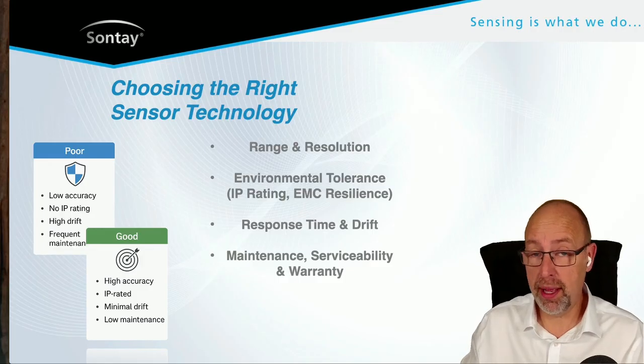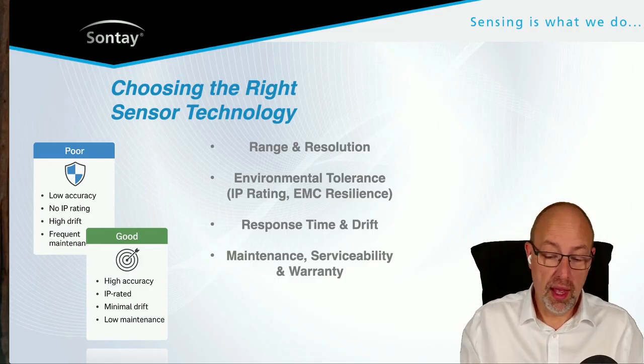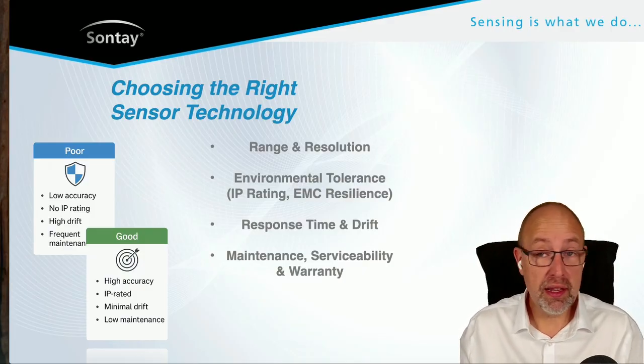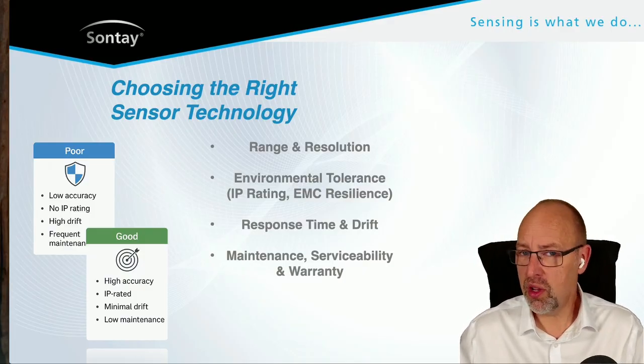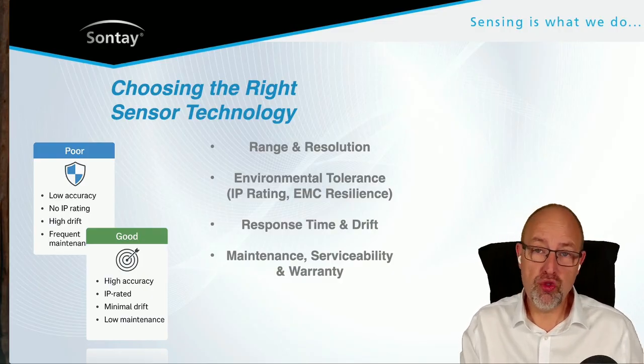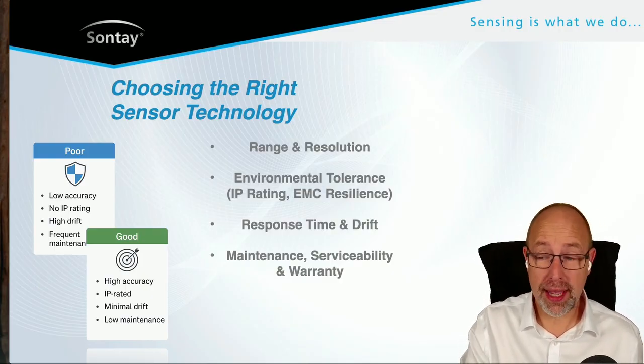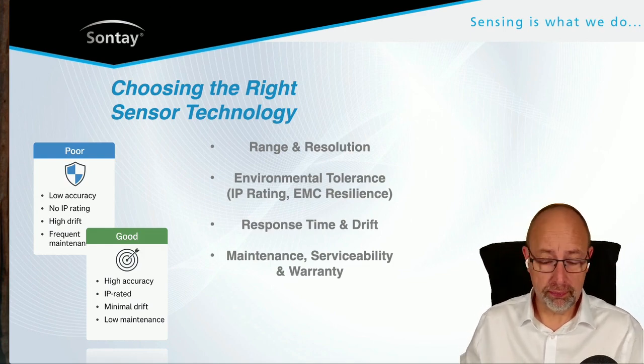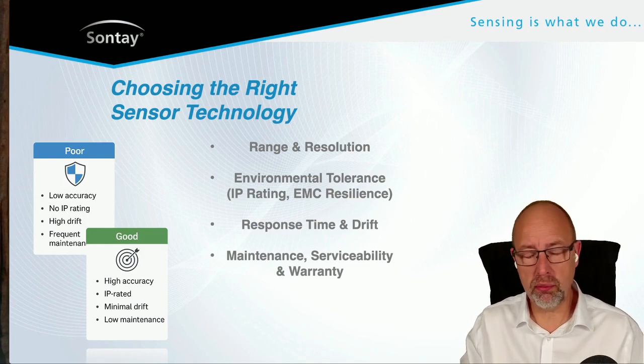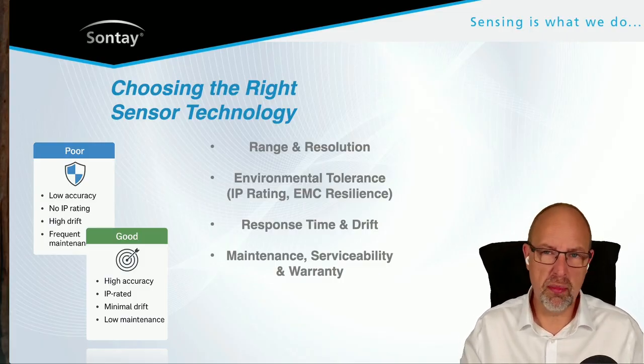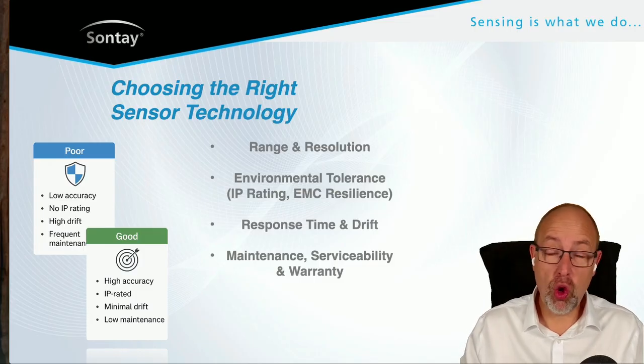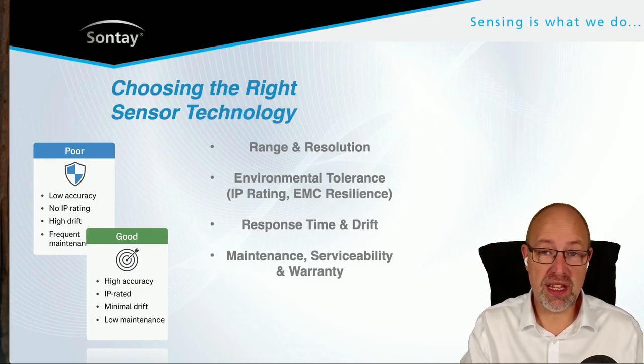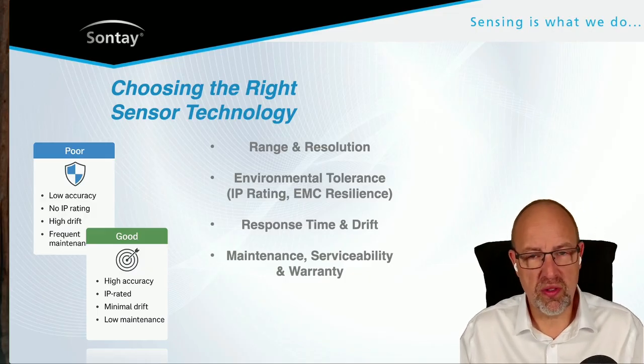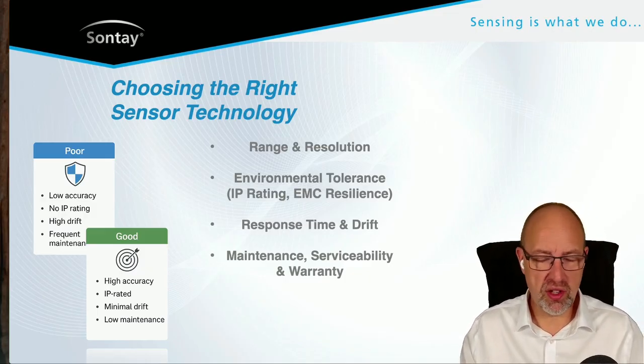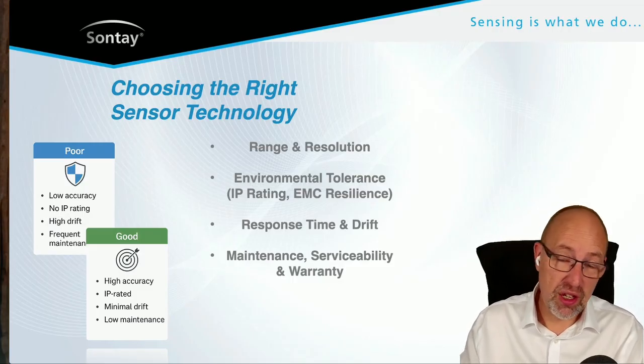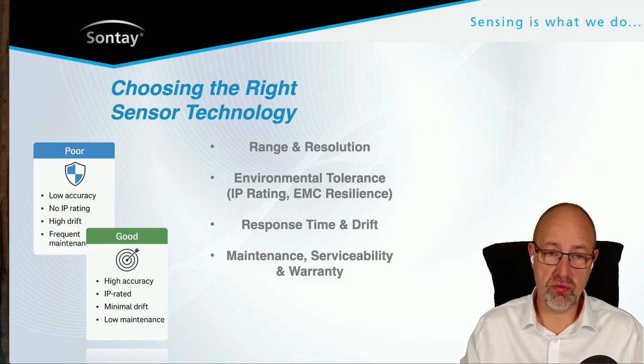Platinum sensors are made out of platinum. They're more expensive than thermistor sensors. But if you are saving millions, if not billions of pounds worth of data, it seems like a small price to pay. So thinking about that is important. Drift over time as well. Now, this goes back to the calibration regime. Sensors do drift over time. Thermistors drift by a very small amount, but they do tend to drift. They have electricity running through them and they break down a little bit over time. If you've got electronic devices, there's a lot more going on there. They tend to drift more quickly, I would suggest by a greater magnitude, but it's not huge. But you need to think about that, and you need to factor that into your calibration regime.